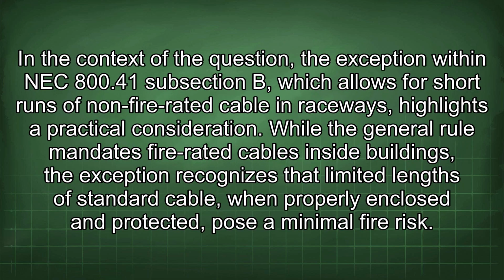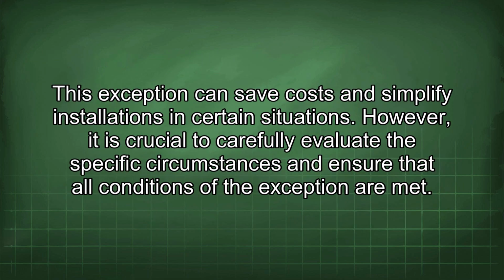In the context of the question, the exception within NEC 800.41 subsection B, which allows for short runs of non-fire-rated cable in raceways, highlights a practical consideration. While the general rule mandates fire-rated cables inside buildings, the exception recognizes that limited lengths of standard cable, when properly enclosed and protected, pose a minimal fire risk. This exception can save costs and simplify installations in certain situations.